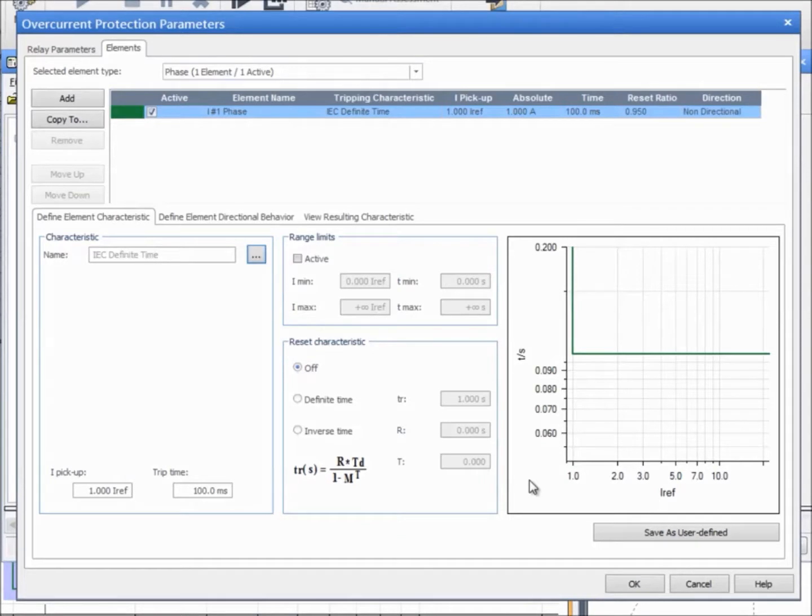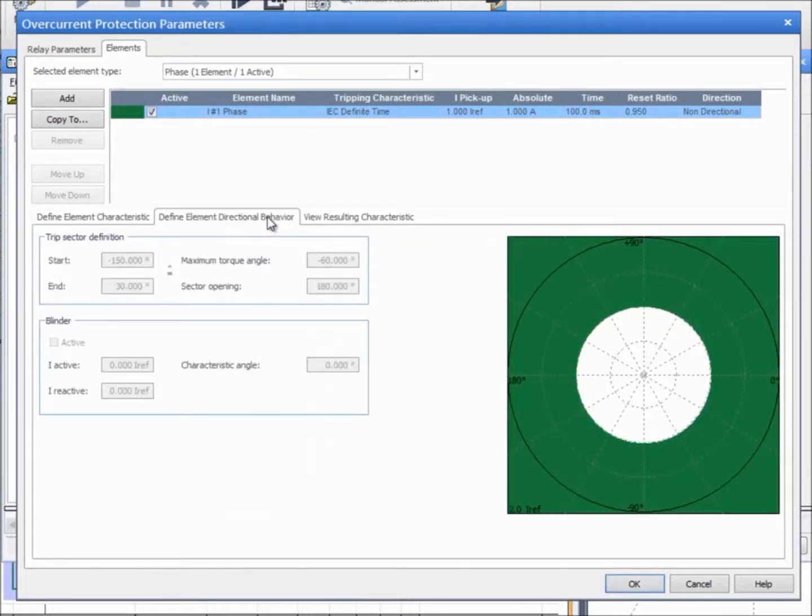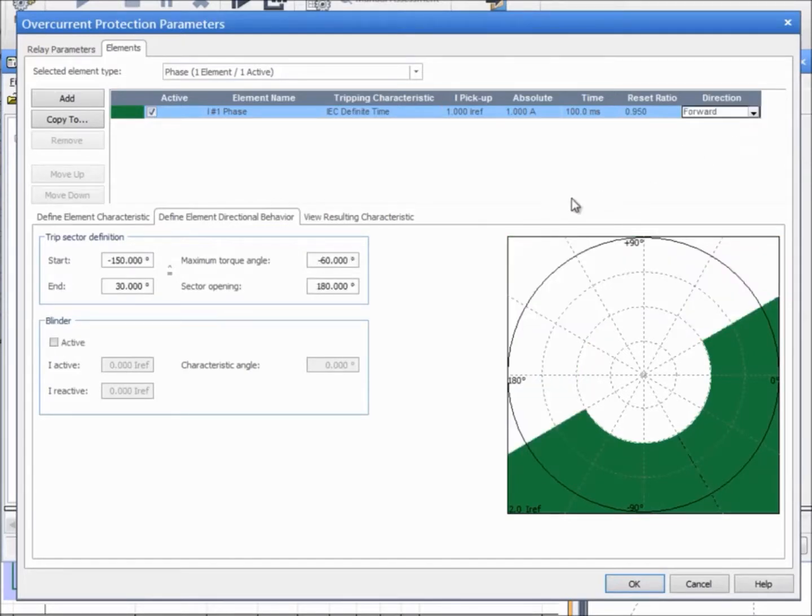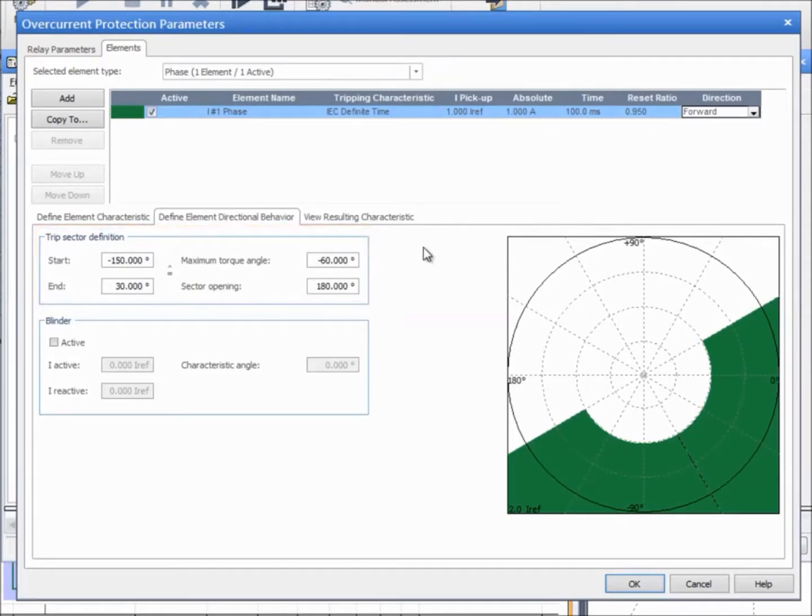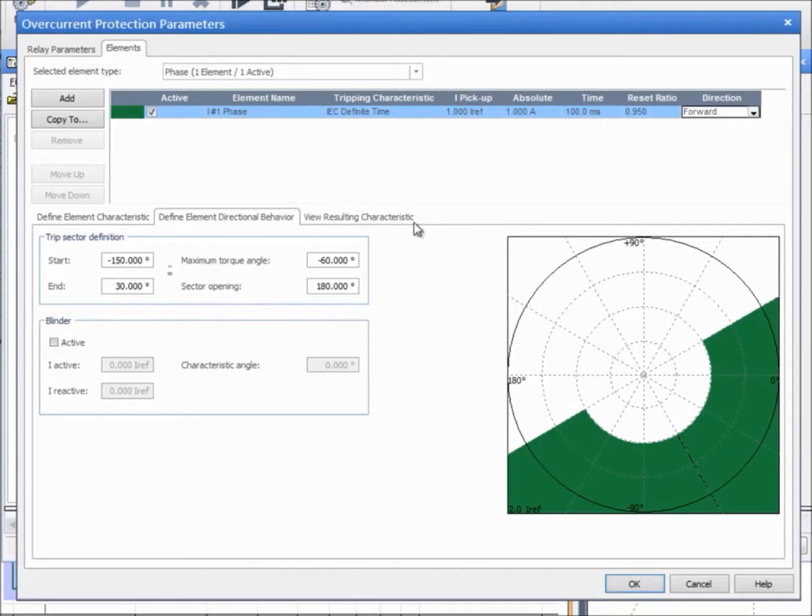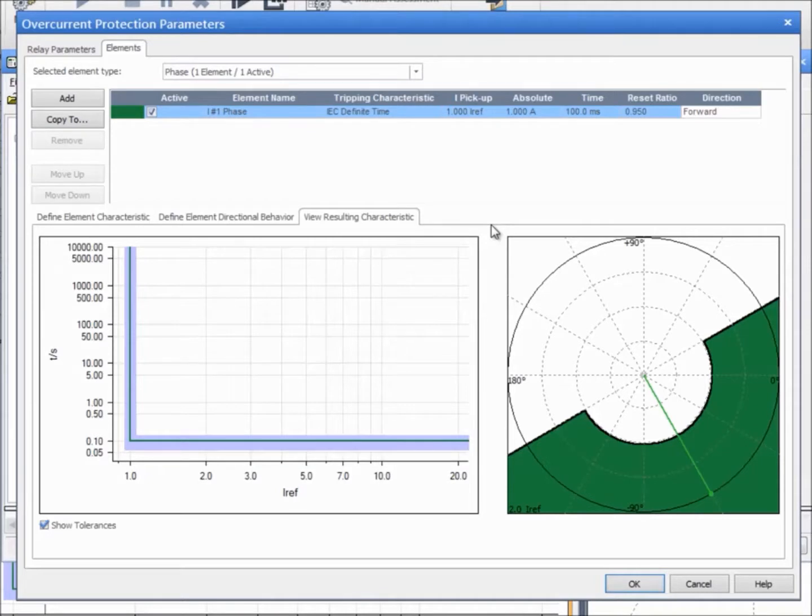If the relay behavior has been set to Directional in the Relay Parameters tab, a new tab will be displayed to enter the corresponding data. The Trip Sector can be defined by its start and end angle or by its direction and sector opening. The Blinder can be used to cut a part of the Trip Sector. A compiling graphic including all the elements and the directional behavior is displayed in the View Resulting Characteristics tab.